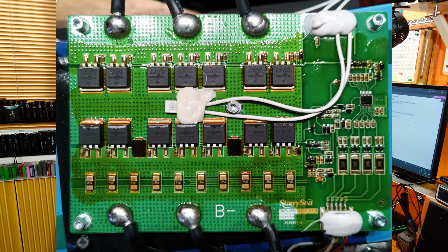The undervoltage protection of the BMS stands at 2.5 volts per cell, which is normal, and overcharge protection disconnects the charge MOSFETs when at least one cell reaches 3.60 volts. I must admit 3.60 is slightly conservative, and it will surely help preserve the cell's life a bit better than the standard threshold of 3.65, which is usual.